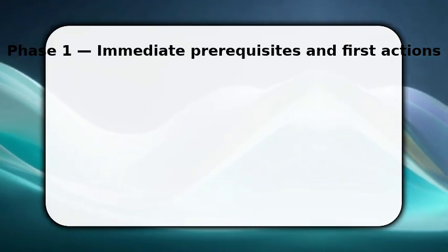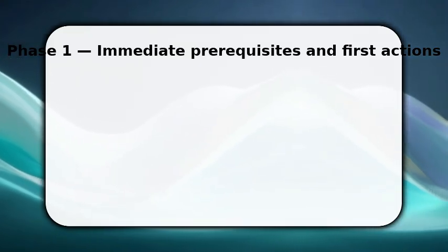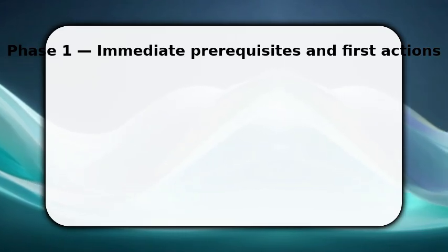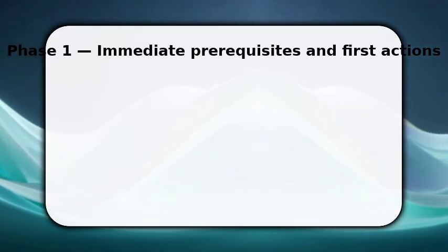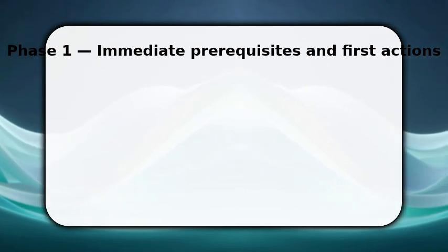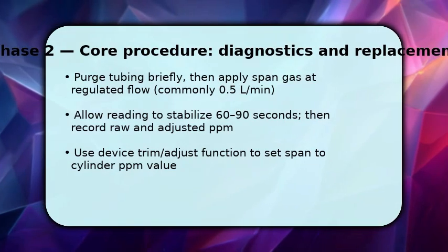Make sure gas cylinder pressures are within range and tubing fits snugly. Now press the mode/menu sequence to access CAL. Then select the gas channel you will calibrate. You now apply the span gas.